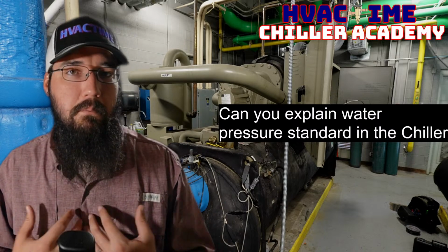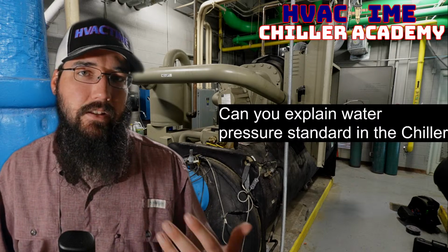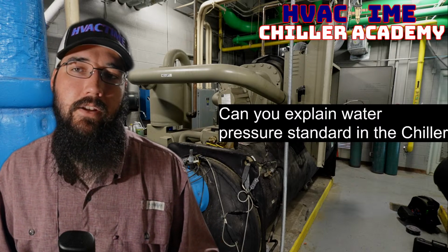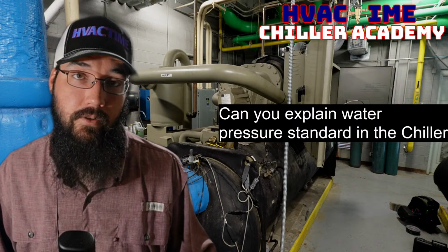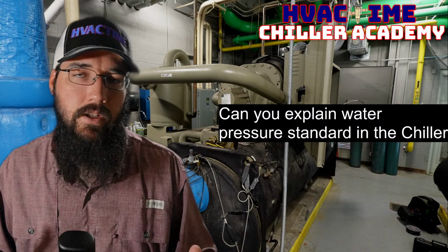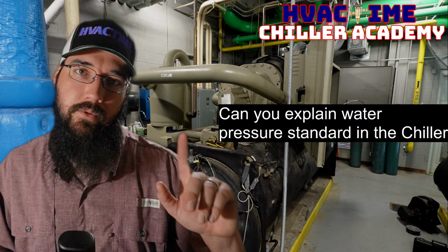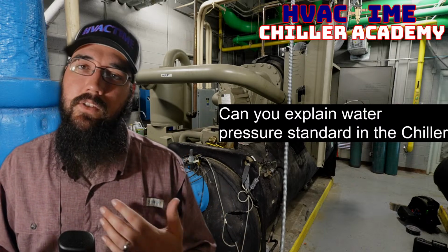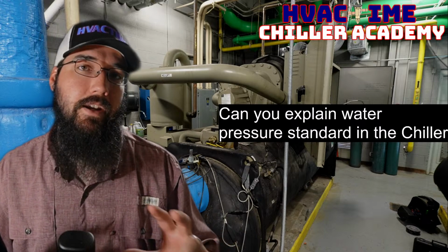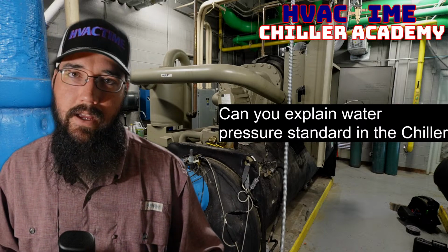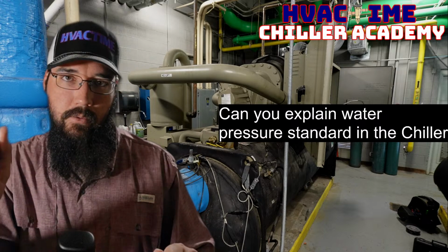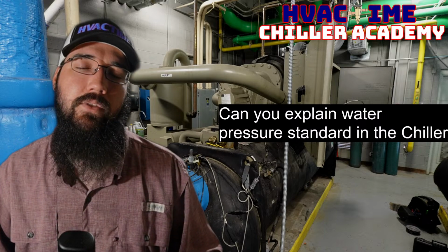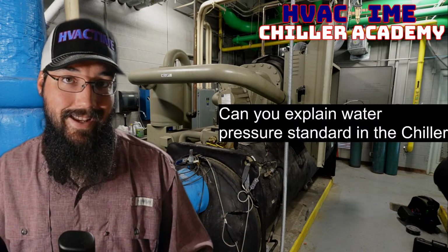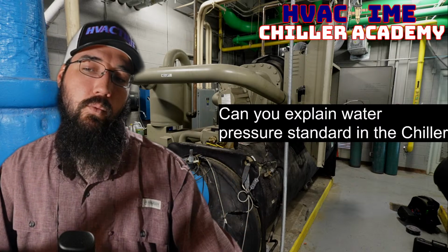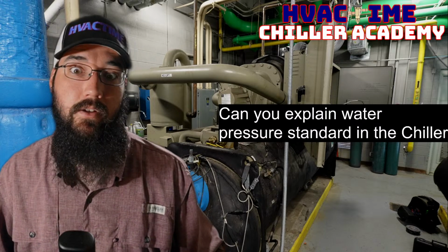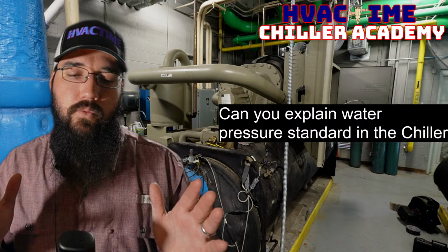But my experience is that you'll get that sometimes, but even then, there's been times where what was written in the panel wasn't correct. Like I later got the actual submittal for that chiller, and it was not what was written in the panel. So you have to be careful with stuff like that, because sometimes people will think they had the actual factory data, or they figured something out, and like, okay, well, this will work, so I'm going to write this down so the next guy knows. I may not have the actual data, but I knew this worked, even though how he made it work may not be correct whatsoever. So that would be a second way.